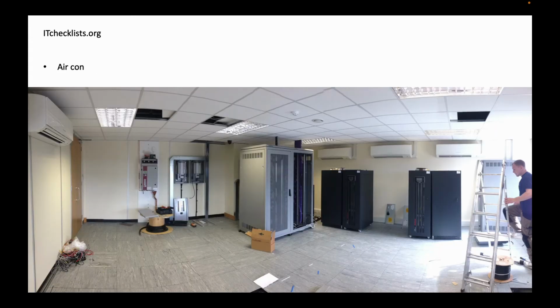We want to make sure there's enough aircon. Obviously, in data centers you're using from someone else, they just take care of this. But sometimes when you're loading up extra hardware, resulting in more and more racks, the aircon starts to get to its limits. So just keep in mind your install might be the one that crosses things over. Aircon shown there on the walls up near the ceiling, separate units, so if one fails the others aren't affected - you have some N+1 there on the aircon.